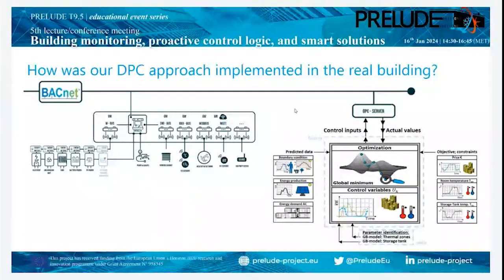Because the DPC approach is an open loop algorithm, we have to consider that the optimization should be done periodically. So in this figure, you see that we made the optimization on an hourly basis, and also the parameter identification with the historical data from the building always at midnight, once a day. So the gray box parameters will be identified once a day at midnight.